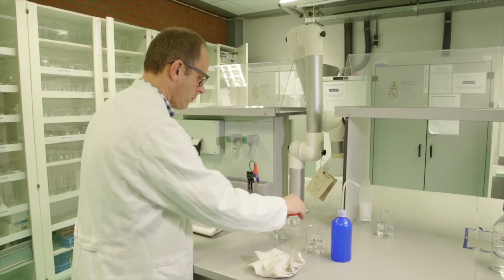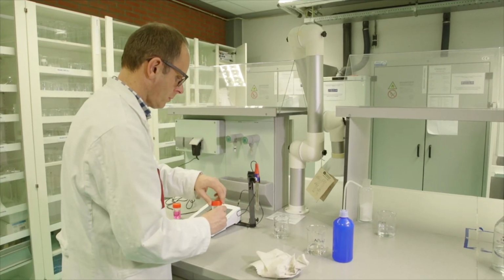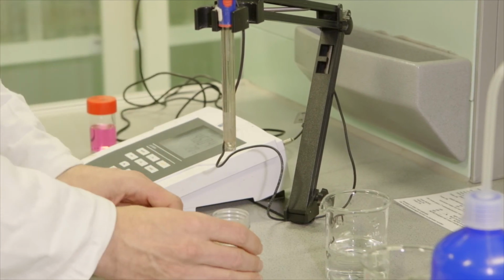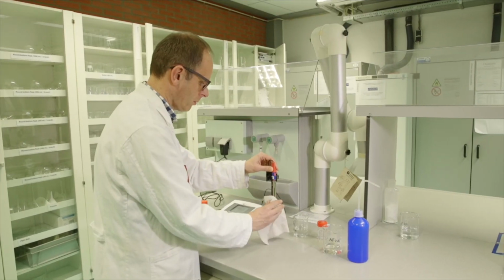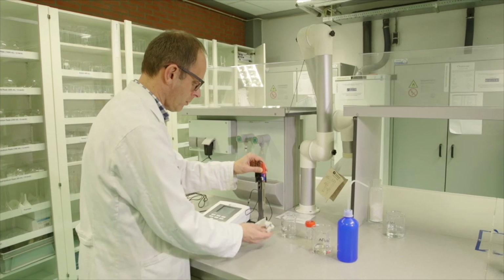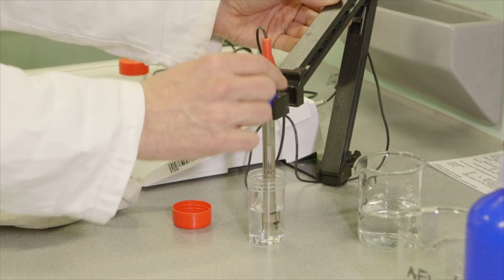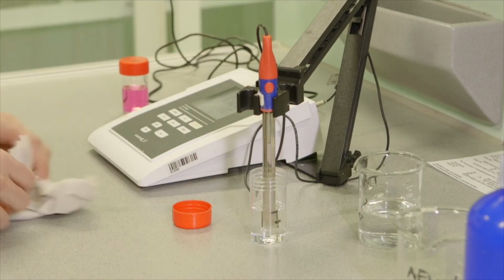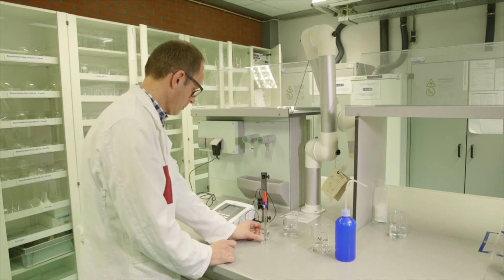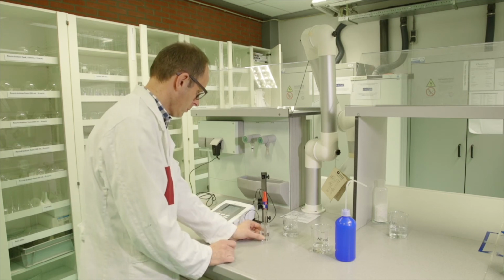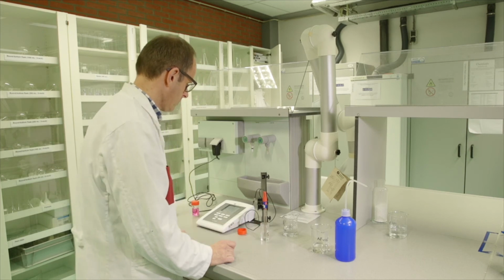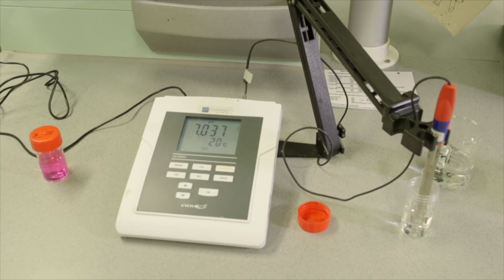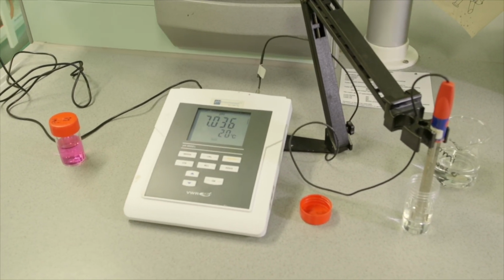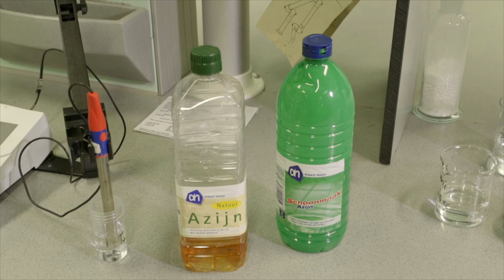Your device is now calibrated. To see if your calibration was successful, you can check if your pH meter measures a pH of 7 when placed in the pH buffer. To do this, we dry the electrode and place this in the pH 7 buffer. Wait for the word auto to stop flashing. When the word auto is no longer flashing, the measurement is stable. The measurement is stable if the measurement deviates no more than 0.05 pH units from pH 7. Now you're ready to start measuring.